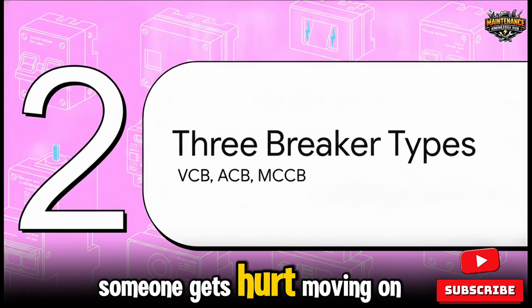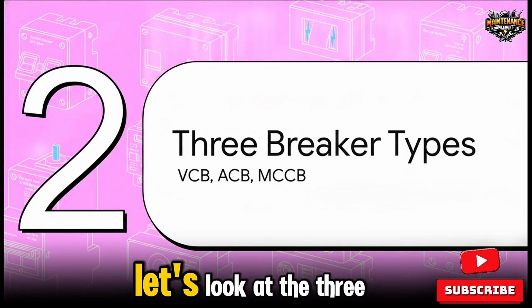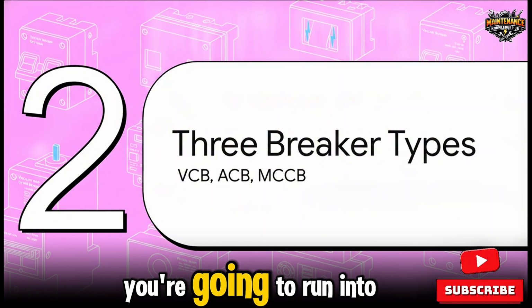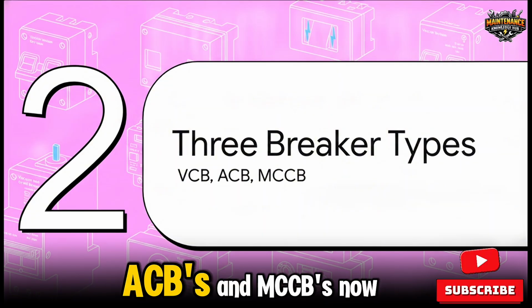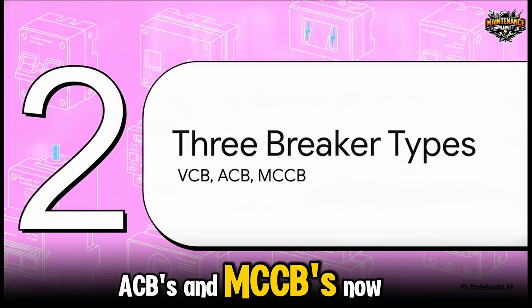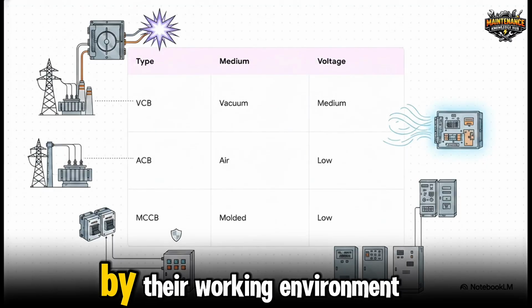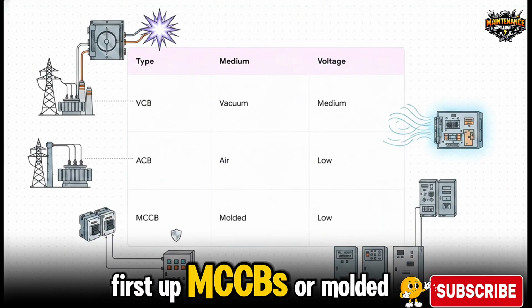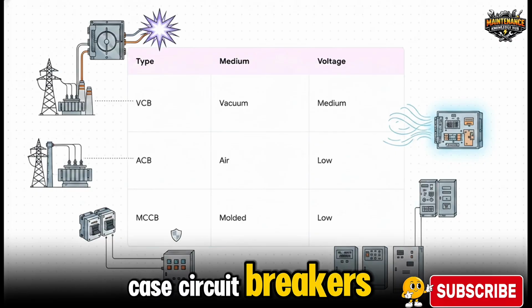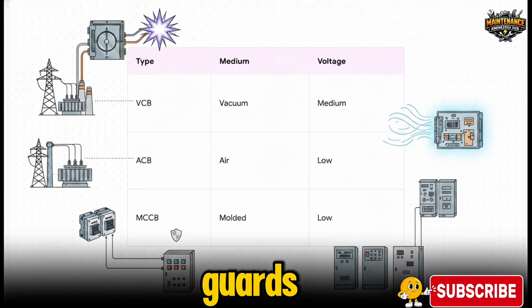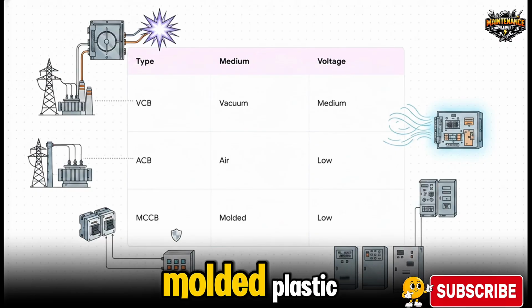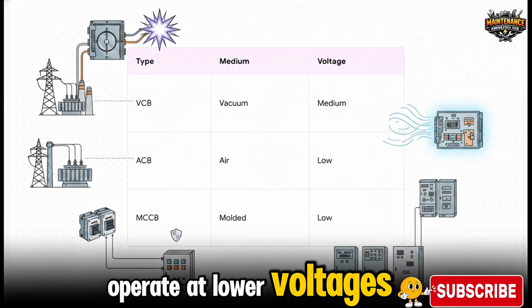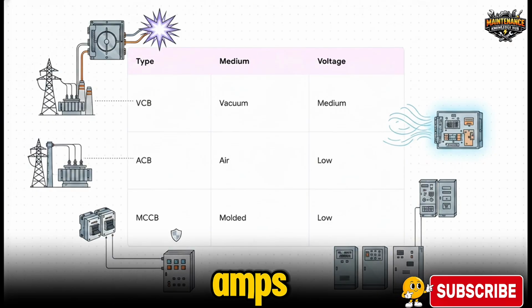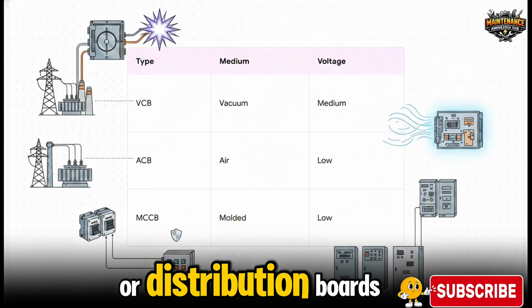Moving on to Section 2, let's look at the three main breaker types you're going to run into: VCBs, ACBs, and MCCBs. Now, I love how this lays it out by their working environment. First up, MCCBs, or molded case circuit breakers. These are your local security guards. They're compact, encased in molded plastic, operate at lower voltages, usually up to about 1600 amps, and you'll find them hanging out at motor feeders or distribution boards.